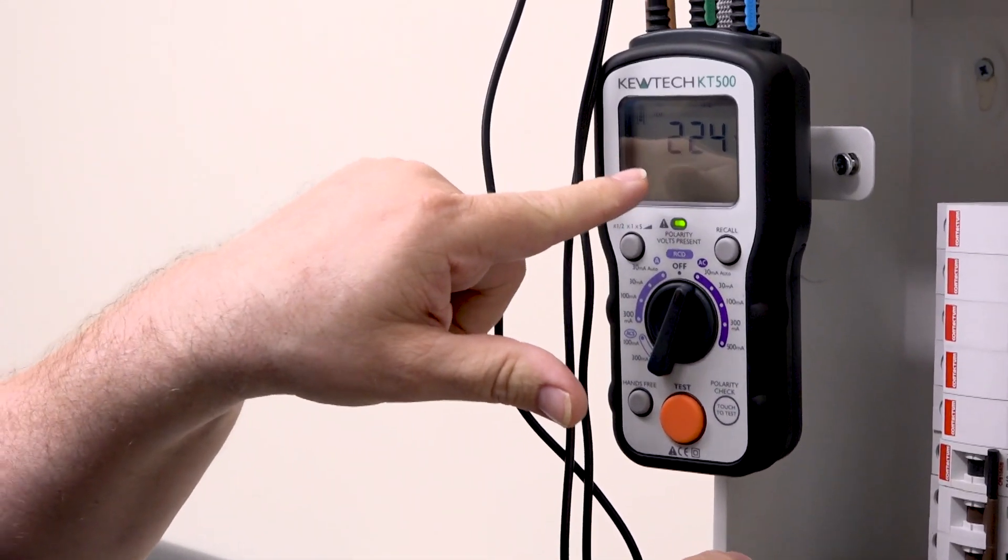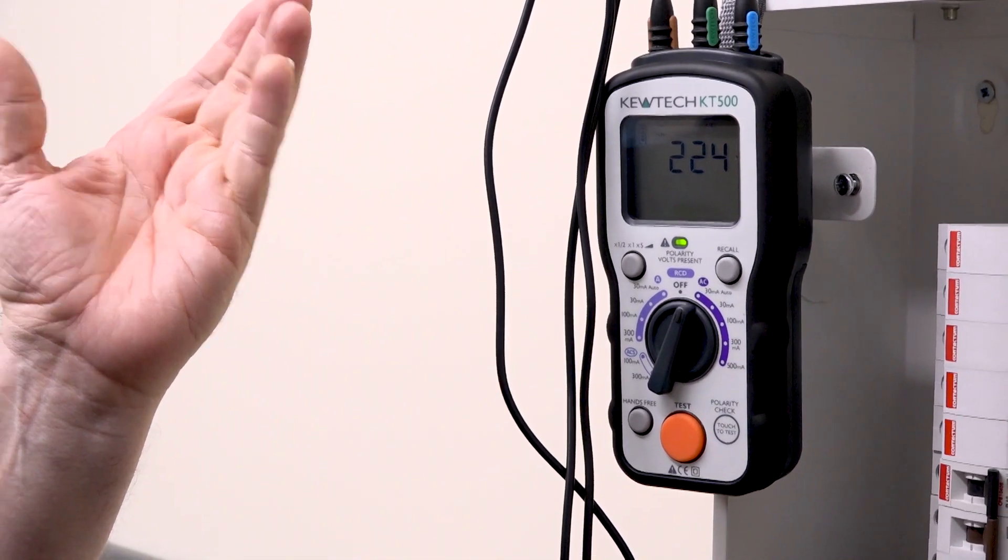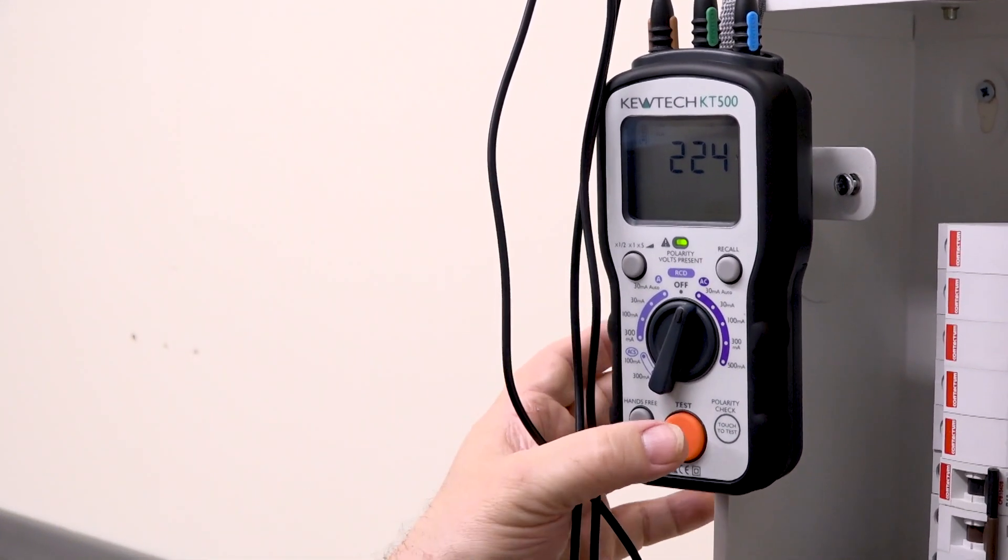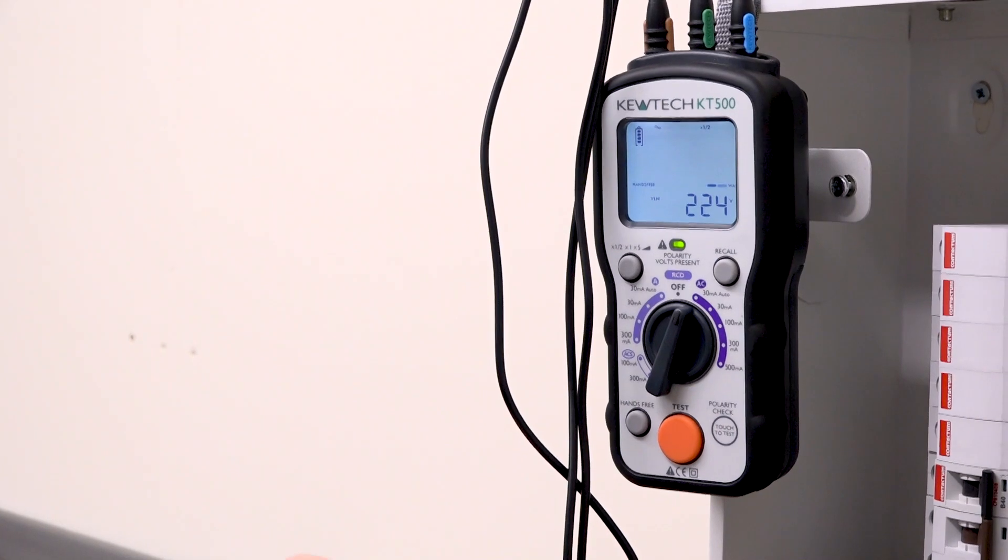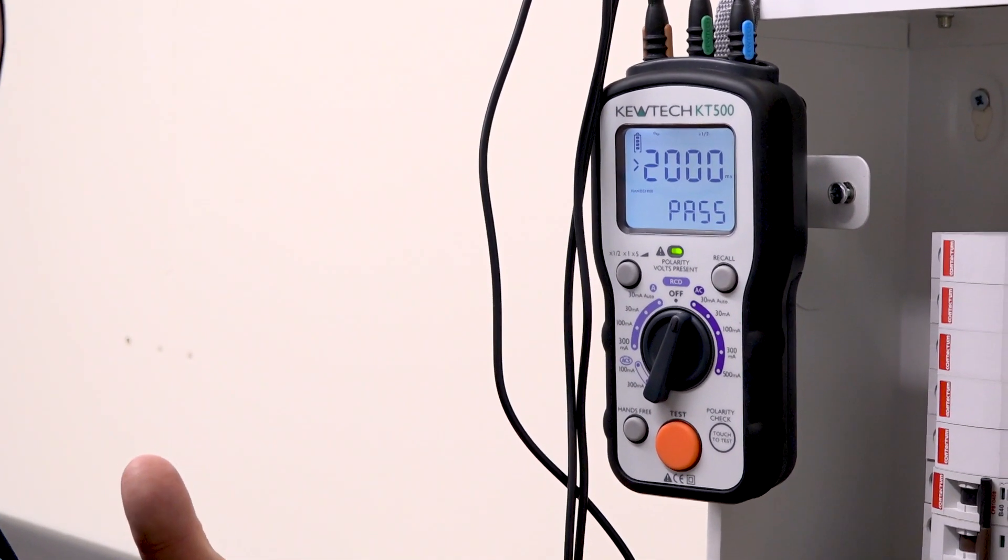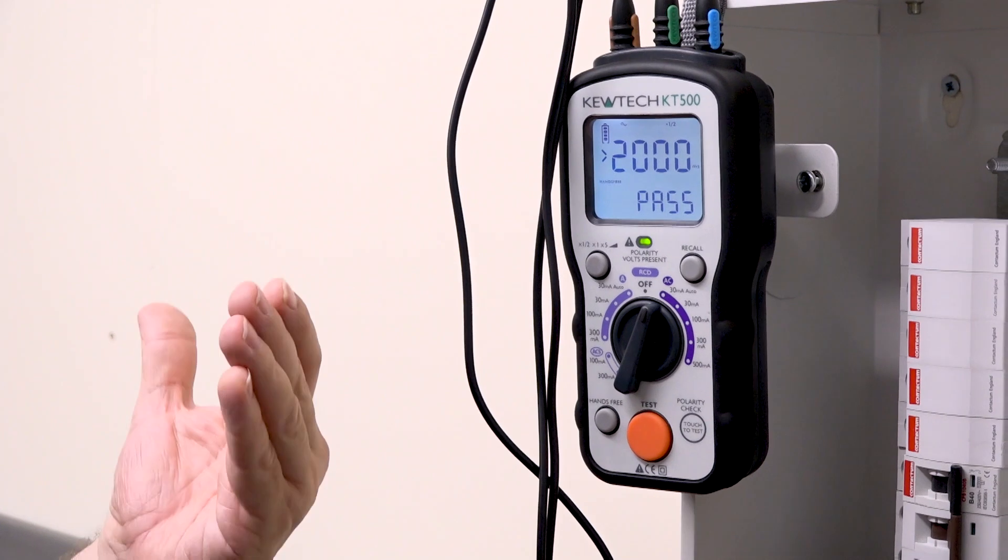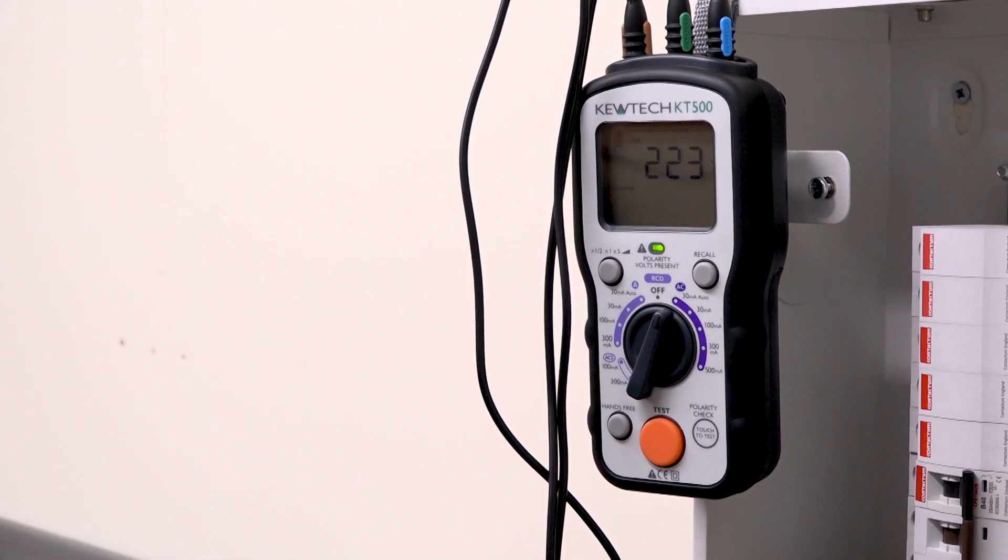And as we can see, displaying the voltage there—224, 223. All we simply have to do, because we're in the auto mode, is press the test. It'll go through the six tests, which is times half at zero degrees, times half at 180 degrees, times one...